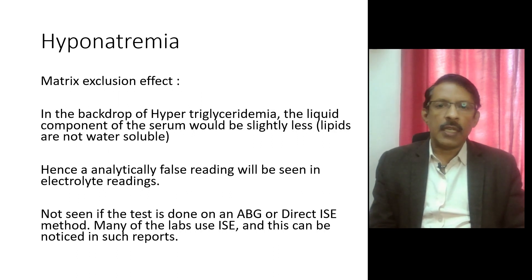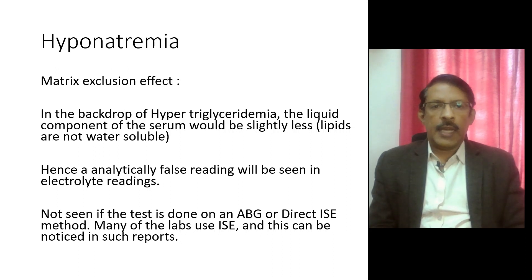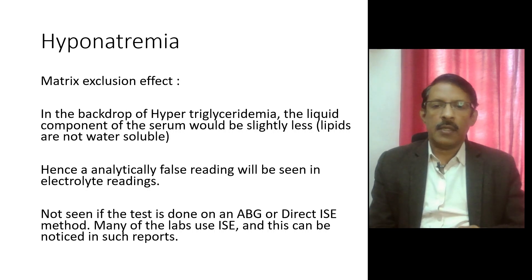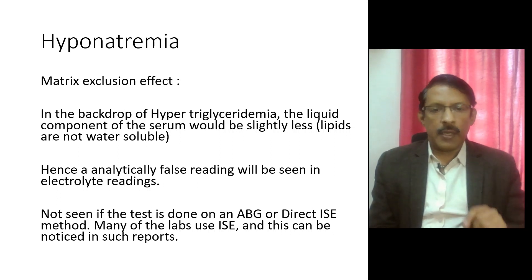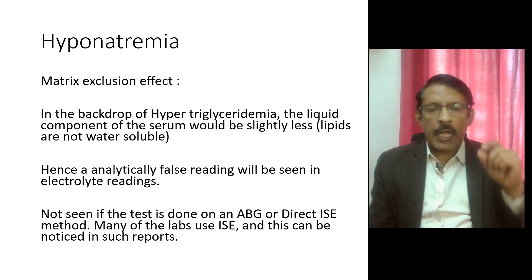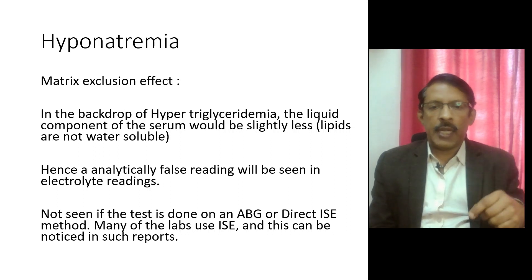Hyponatremia can also occur due to another condition called the matrix exclusion effect. There are two kinds of electrolyte analyzers in the lab: one called the direct ISE (ion sensitive electrode) and one which is the indirect ISE. Most labs usually have indirect ISE. The arterial blood gas analyzer, which also gives electrolyte levels, works by the direct ISE. The key difference is that in indirect ISE, the plasma or serum is diluted and then we estimate the electrolytes in the diluted version.